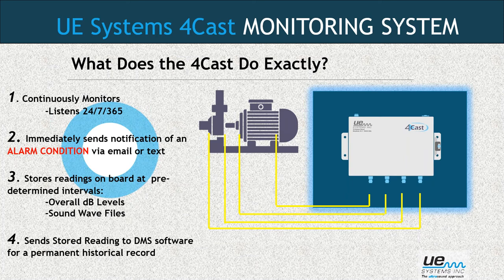The last thing it does, it sends those stored readings over to DMS software for a permanent historical record. So if the motor's running along fine, nothing happens, we're taking a reading every day, maybe we tell it to send over a stored reading from the box over to the software once a month. The beauty of the system is it's not going to miss anything because it's always listening.